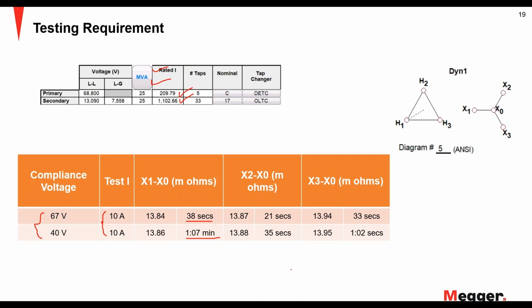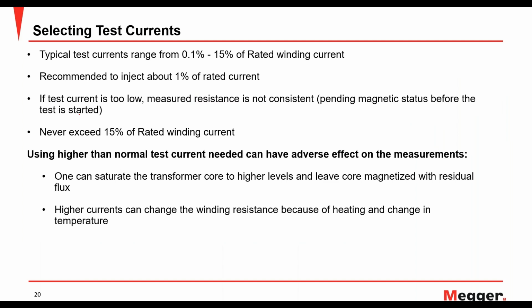So that's what it's explaining: based on the voltage or current of the transformer, select an appropriate current to stabilize. Now, how much current should I select? The rated winding current is typically determined by the MVA and kV rating on the transformer. Whatever your rated winding current is, select 0.1% to 15%. Never exceed 15%. Anything between 0.1 and 15 is fine, and it is recommended to inject 1%. So if my rated current is 100 amps, I would just inject 1 amp.